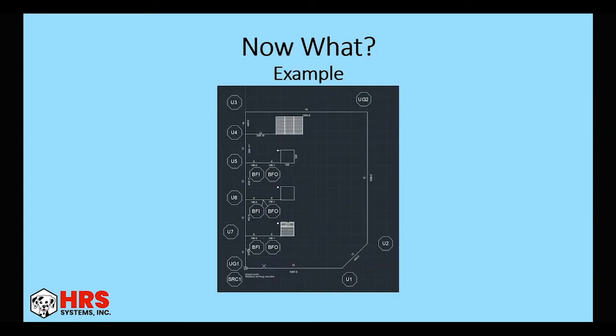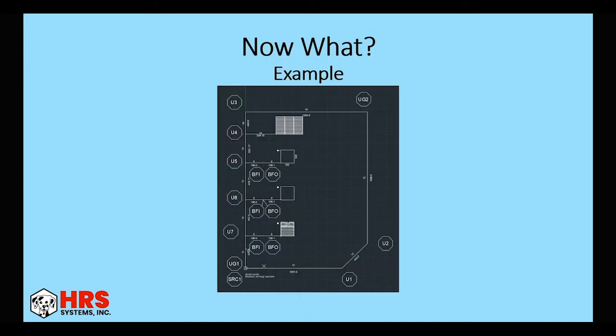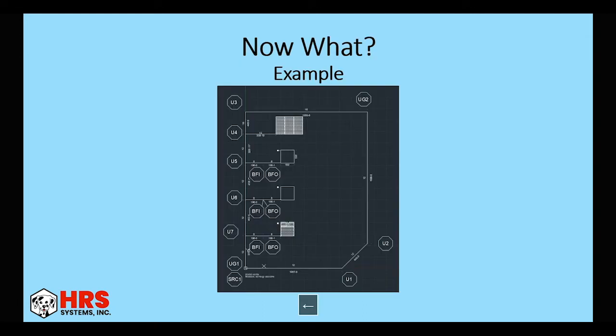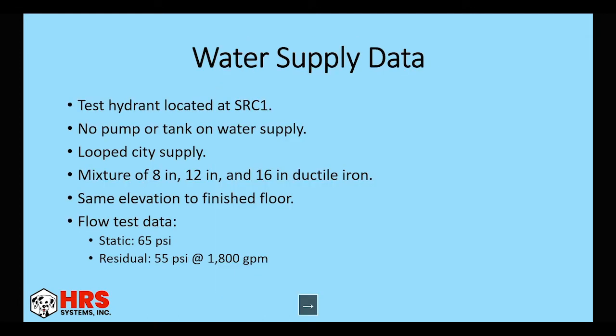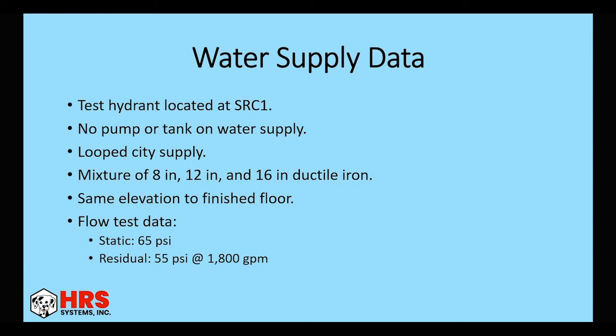So here's the floor plan we're going to be working with. So our test hydrant is located at SRC1, which is at the bottom left-hand corner. No pump or tank on the water supply. As you can see, it's looped. It's a mixture of 8-inch, 12-inch, and 16-inch ductile iron. And then to keep things simple, we're going to say the test hydrant is at the same elevation as the finished floor. Our flow test data, static 65, residual 55 at 1800 GPM.